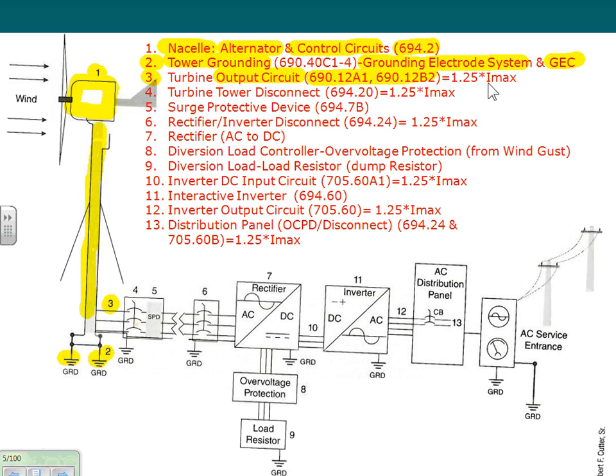So we can size this equipment, buy it, install it, and fix it. If you go through this, it will tell you, and I'm sure the masters and electricians here know this by heart. We take the maximum current that this turbine can provide at the maximum voltage and maximum power. So if this turbine is 25 kW, and that's the maximum power that it can provide at say 480, 490, you take the 490 instead of 480, the maximum voltage. You divide the power by the voltage, and with a power factor, you find the maximum current. Most of the time you either calculate it or find it right on the nameplate of the equipment. So we got our maximum current, and we multiply it by 1.25, the continuous load multiplier, typical in all electrical, a safety factor, and based on this, you size your conductors. Really no rocket science to it.